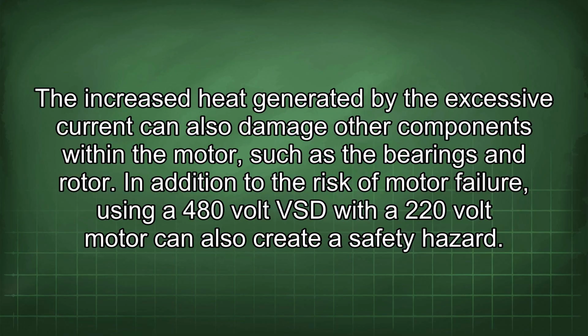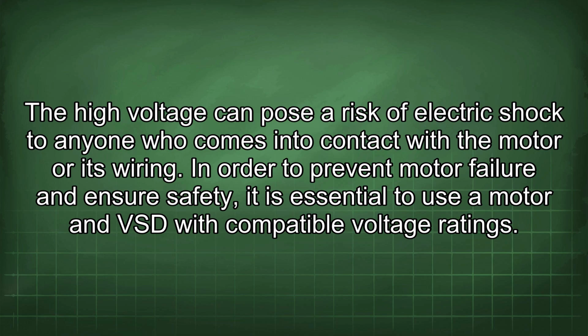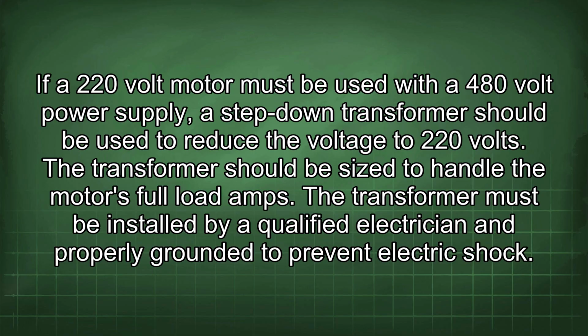and rotor. In addition to the risk of motor failure, using a 480-volt VSD with a 220-volt motor can also create a safety hazard. The high voltage can pose a risk of electric shock to anyone who comes into contact with the motor or its wiring. In order to prevent motor failure and ensure safety, it is essential to use a motor and VSD with compatible voltage ratings. If a 220-volt motor must be used with a 480-volt power supply, a step-down transformer should be used to reduce the voltage to 220 volts.